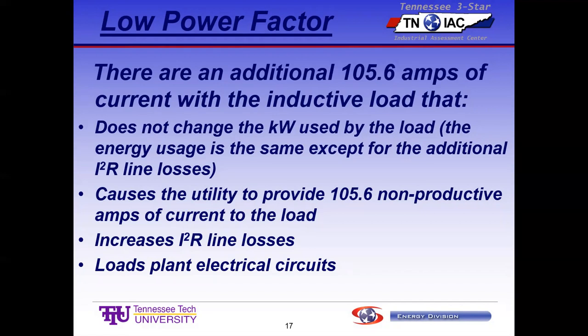And the other thing that happens in a plant is sometimes their distribution system will be maximized. Like they've got what they call an MCC, a motor control center, that all the power flows through to this part of the plant. And they want to add another load. And the electrical guy comes in and says, hey man, that thing's pulling 429 amps and it's rated for 440, and you can't put another load on there. Well, you can go to those existing loads that are fed through there, and if you can correct some power factors at the motor, you can put the capacitors directly on the motor, and it'll correct it there, and it'll reduce that current flow through that MCC.